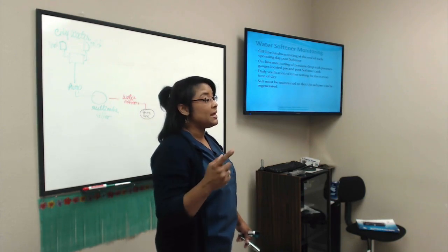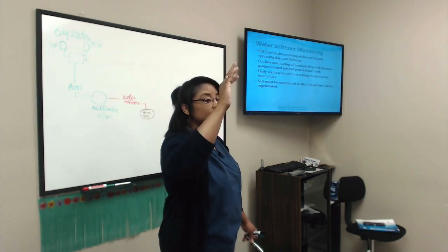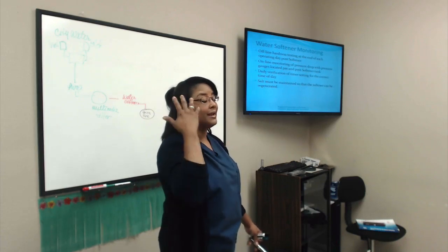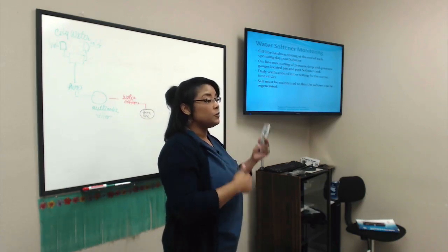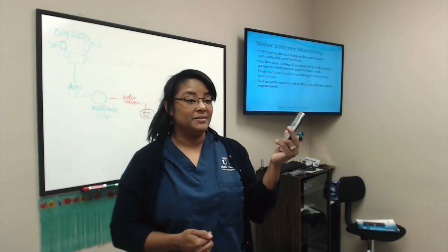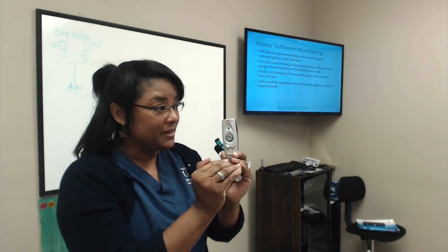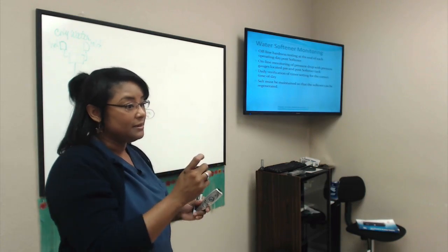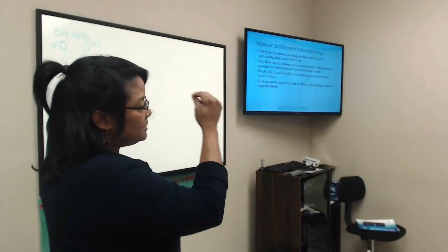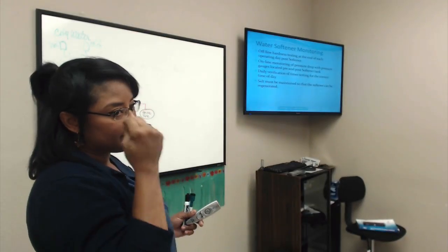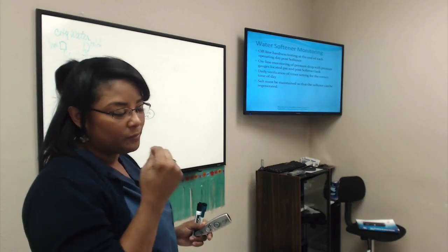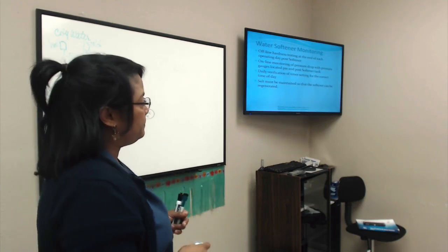Remember that it's cleaning itself, so it's releasing things that had already been filtered. So we are exposing patients if that happens. So that time has to be accurate, and if it's not, change it. So that's why everything that you are checking in that dialysis water room is important.